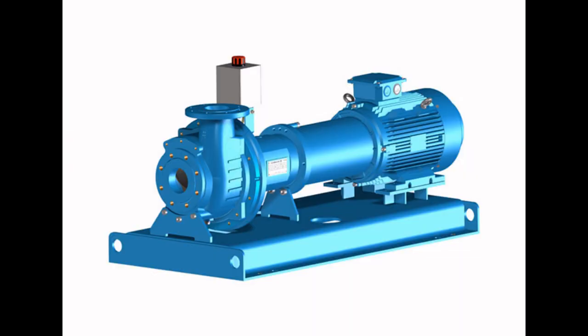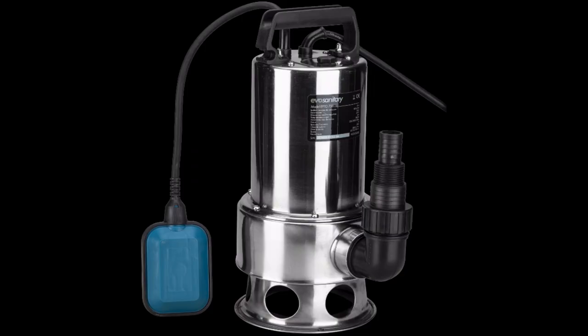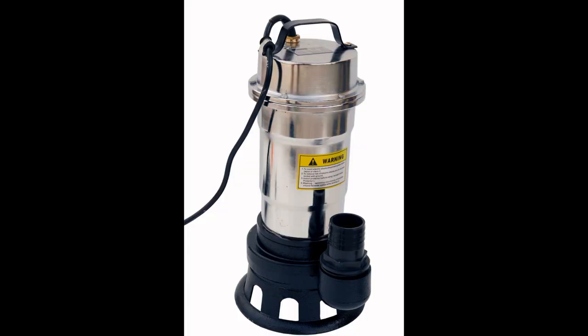5. How do we choose a submersible pump? The pumping height, to how many meters we want the pump to raise the water column, and the water flow required at that height are taken into account. Attention: from the pump operating curve, the flow rate will be chosen depending on the pumping head. It is recommended to choose a pump somewhat more powerful than what results from the calculations, so that it does not have to work at maximum load. When you choose a water pump, make sure that it meets the requirements regarding the flow rate and discharge height and respects the economic principles, security and applicability depending on the use.